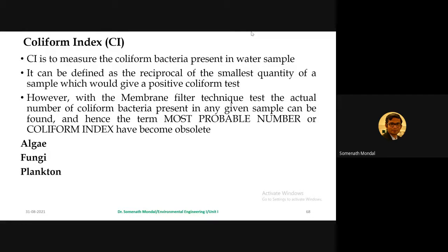Now, large quantities of plankton may impart a green, brown, or yellow hue in the water, so that is also very true. They sometimes interfere with the smooth working of the rapid gravity filters by preventing the proper accumulation of alum or floc on sand. And if those kinds of planktons are present in the water, then white porcelain utensils or porcelain attachments in the kitchen and bathrooms will get yellow stains. That happens because of those planktons, and they need to be cleaned or eradicated before you send that particular water into the distribution system.